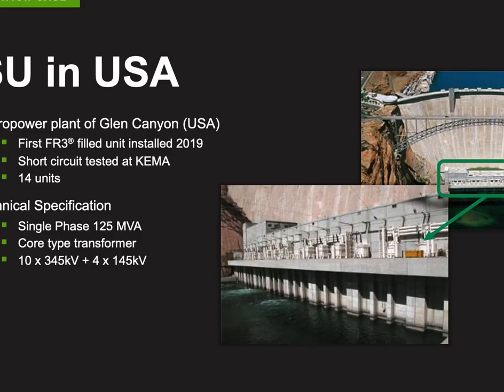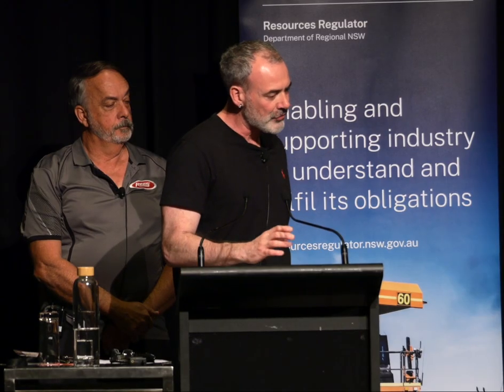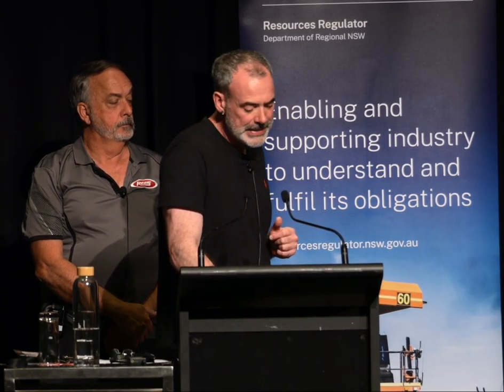Just a quick case study. This is an example of a major project in the USA using a natural ester fluid. The Glen Canyon Dam was built in the 1950s and 60s. All of the transformers were replaced recently. Our natural ester was used in the transformers, and the reason for this is the proximity of the transformers to the river, which is a drinking water source. If you look at the voltage class, you'll see they're pretty big transformers, 125 MVA, 345 kV, 145 kV. Also in Australia, we see ester fluids being used in transformers on the coasts of rivers.